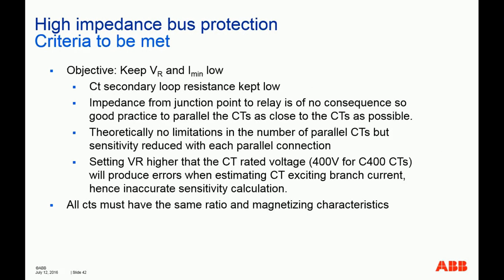The reason is that for voltage higher than the rated voltage, on the excitation curve, the CT has already entered or is beginning to enter saturation. So the excitation current is not linear anymore. A small increase in voltage will increase that excitation current by a big margin. So it would not be accurate anymore to derive that exciting current from the curve. That's why there will be errors when you are estimating the sensitivity of the CT.